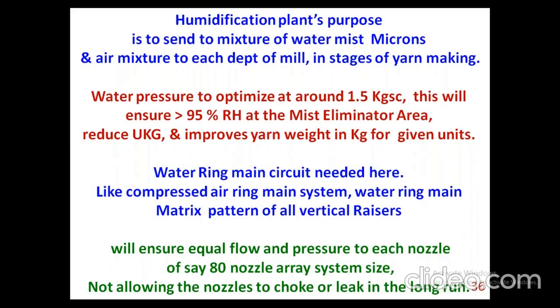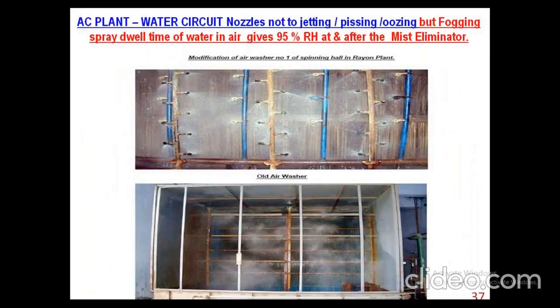Here, in fact, having done energy audits in all the mills, we have suggested this, but many of the mills did not apply this concept. We have done the ring main concept in all the compressed air headers, but we have to do the ring main concept on the water also. I'll just show you this one slide. You can see the ring main concept that is done totally. All the vertical riser pipes are to be joined. At the top, the nozzles are all jetting. The water is coming so heavily at a high pressure.